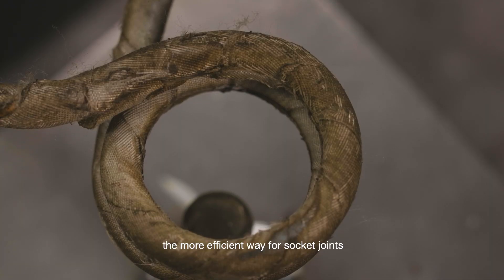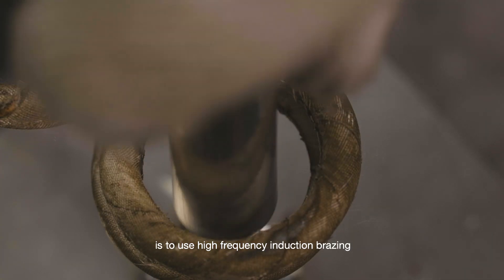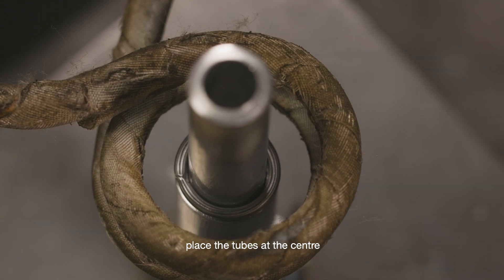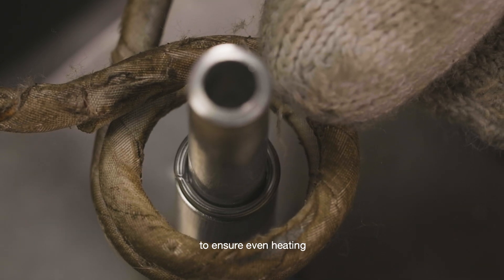The more efficient way for socket joints is to use high-frequency induction brazing. Slide in a flux-cored brazing ring of compatible size. Place the tubes at the center of the induction coils to ensure even heating.